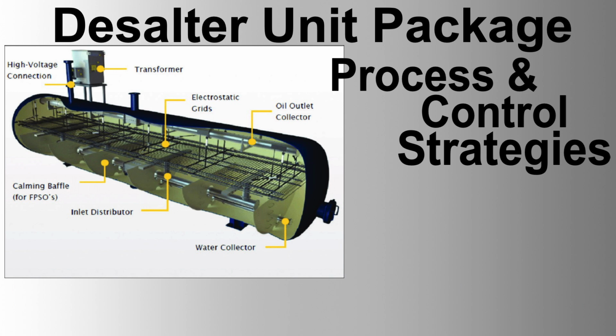3. Low-voltage shutdown. If the voltage applied to the electrostatic field drops below a certain level, the voltage controller VC401 triggers a low-voltage shutdown, stopping the crude oil flow to prevent inefficient desalting. Operational procedures. Startup procedure. 1. Pre-startup checks. Ensure that all control systems and instruments are operational. Verify that the crude oil inlet and brine outlet valves are in the closed position. Check the electrostatic field system for proper functionality.